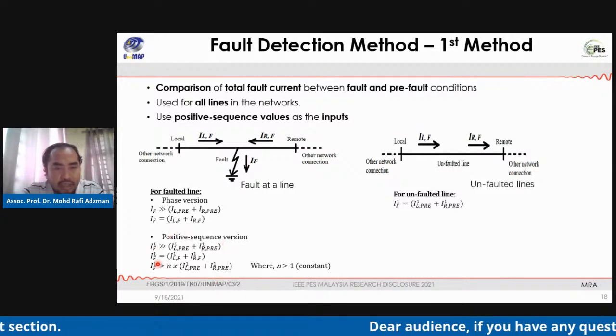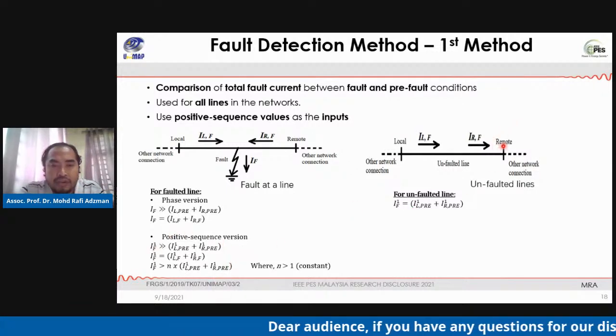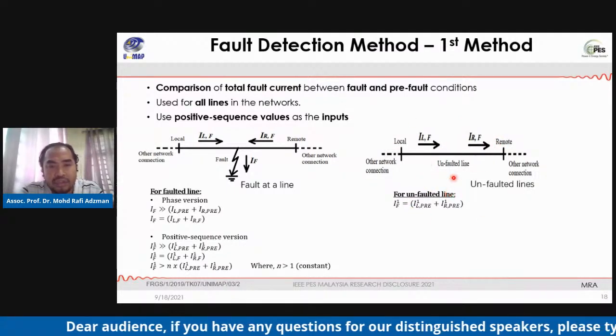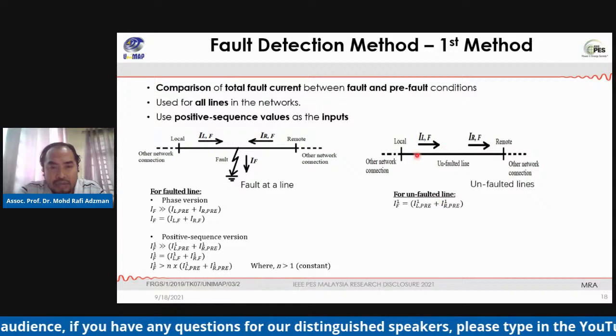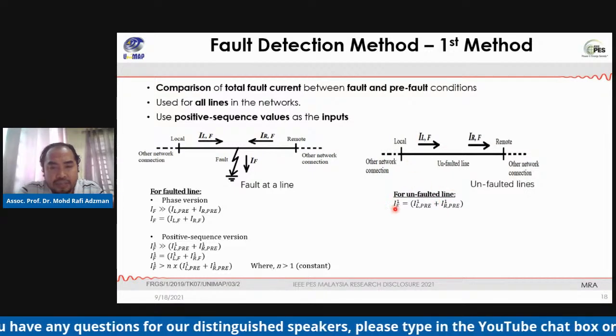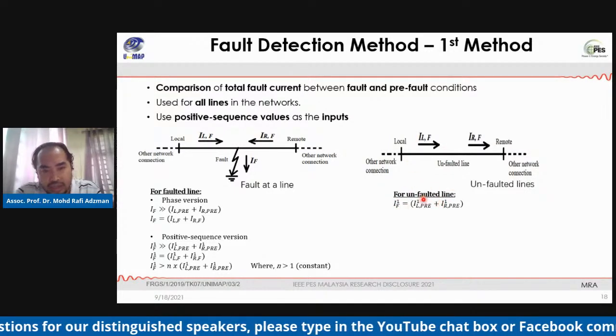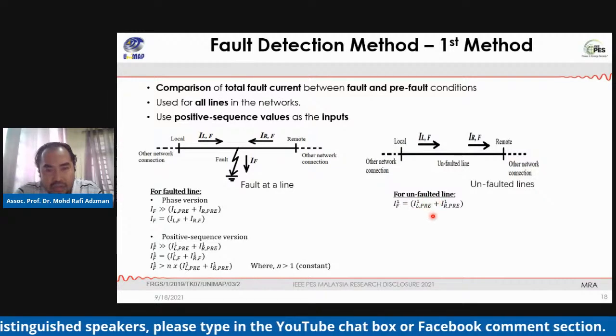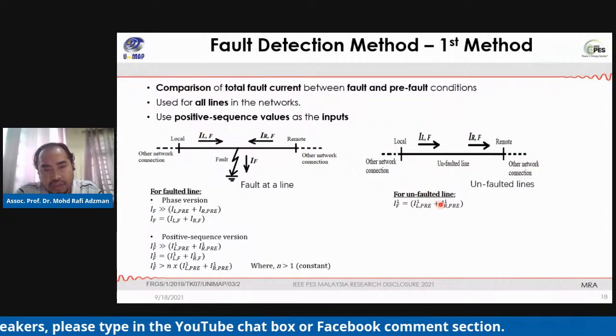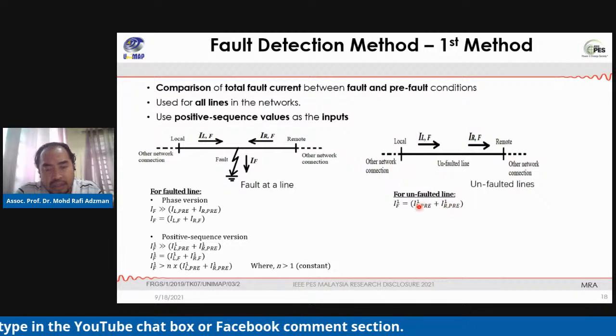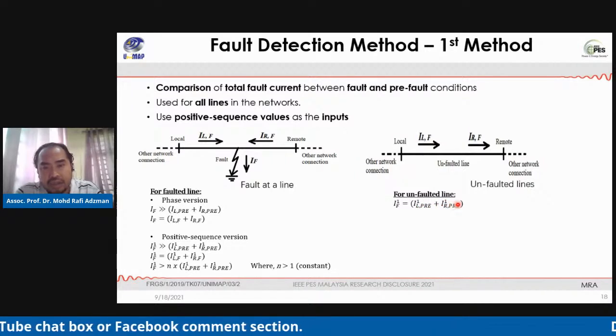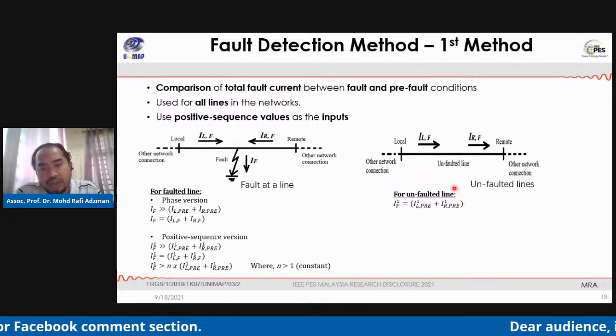Here are the equations. We compare against the unfaulted lines. For the unfaulted lines, the positive sequence current is equal to the pre-fault positive sequence local current plus the pre-fault positive sequence remote current.